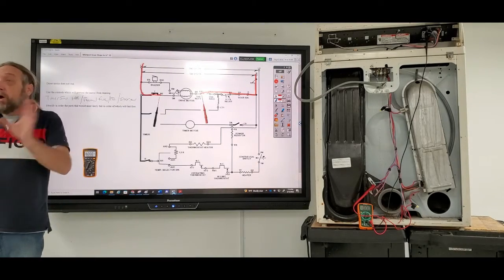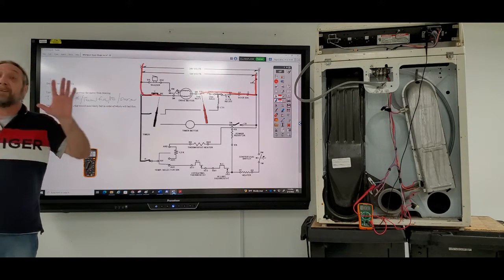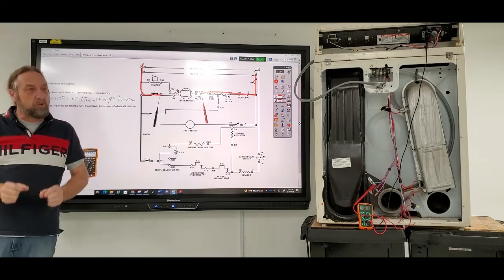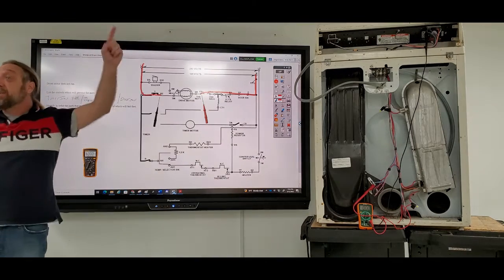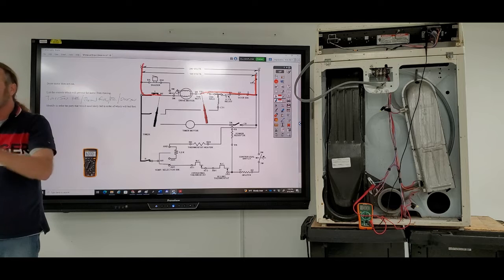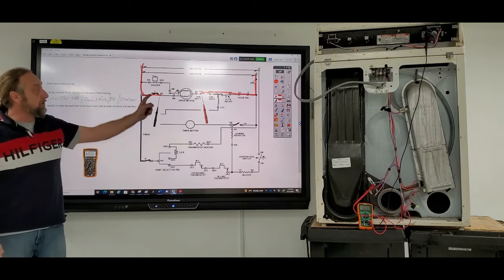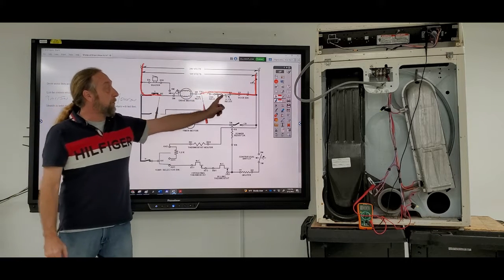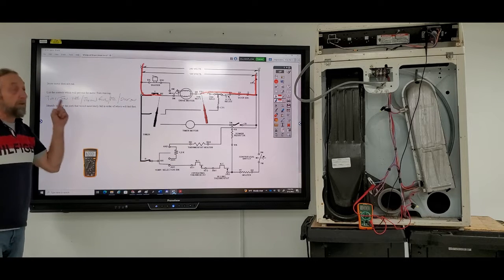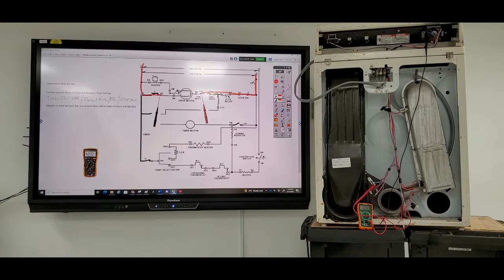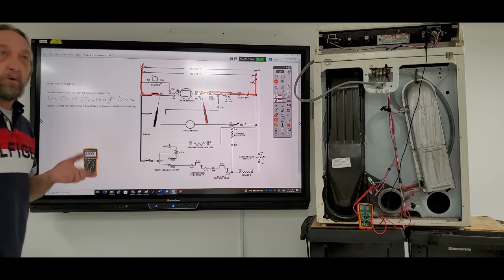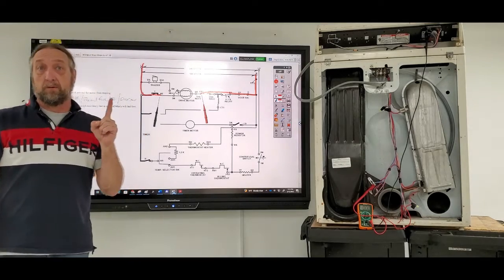I don't know which side is broken if I don't have voltage, but if I do have voltage, it tells me everything up to that point is good. It's telling me my timer switch, my thermal fuse, my relay, and my door switch. So basically, every single thing that I wrote down there is good. One test, voltage. Second test, here, boom. I've just eliminated every one of those components in the circuit with one voltage test. Okay, I see what you're saying.